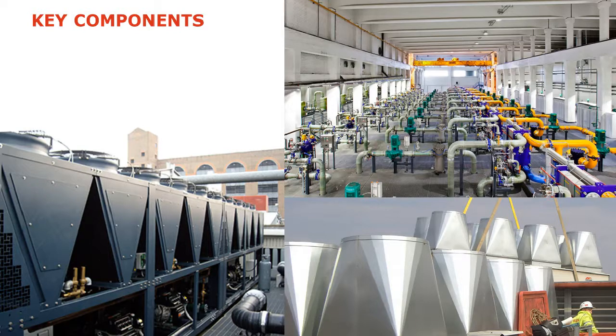Yeah, I think certainly in my time looking over the industry, we've gone from using about one kilowatt for cooling services for every kilowatt we use on IT. Now we're really seeing that efficiency as a tenfold decrease. So for every kilowatt we're putting into IT equipment, we're only using 100 watts in some facilities now that are really pushing the boundaries. And that's been great to see.